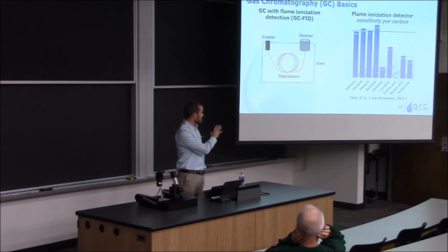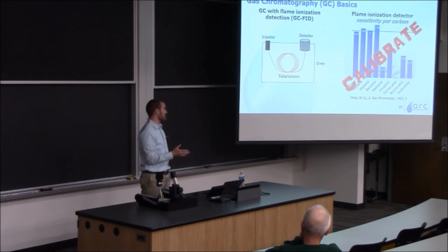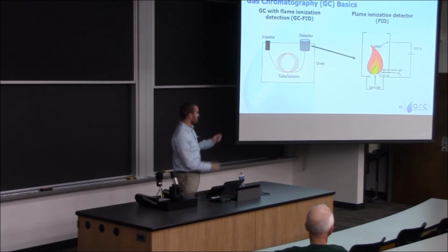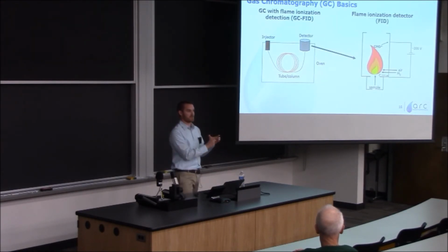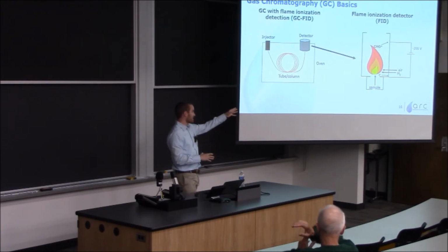So in order to study these compounds, you need to calibrate the FID. And these response factors can actually change depending on which FID you're using, because inside of this flame you're actually doing hydrogenolysis reactions. Those hydrogenolysis reactions that split the molecules depend on the temperature, the hydrogen, and the air that's in there. So you need to calibrate your FID before each experiment.